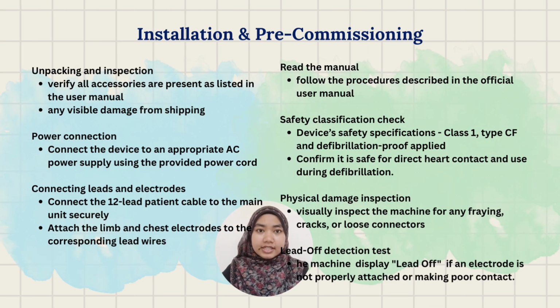Next, installation and pre-commissioning. First, for installation, unpacking and inspection: verify all accessories are present as listed in the user manual, and look for any visible damage that can happen during shipping. Second is power connection: connect the device to the appropriate AC power supply using the provided power cord. Third is connecting the leads and electrodes: connect the 12-lead patient cable to the main unit securely and attach the limb and chest electrodes to the corresponding lead wires.